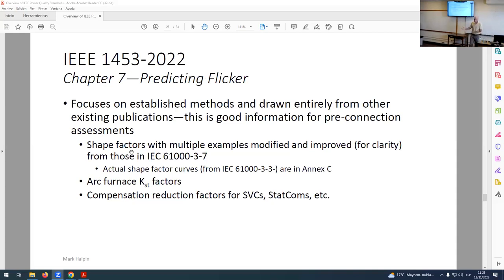As far as predicting flicker, flicker's great. We can go measure Pst after the system's operating and all the customers are doing whatever. But how do we predict it ahead of time? Okay. Well, there are existing ways to do this, particularly coming from the Eurozone. But we didn't have those. We didn't have that in IEEE. Okay. So when we were putting 1453 together, we went out and made a collection of all these different resources, and we included ways to predict the flicker effects, shape factors developed by the IEC and published in 61000-3-3 and -3-7. Right? Shape factors, we brought those over and educated, you might say, the U.S. community on how to use them.